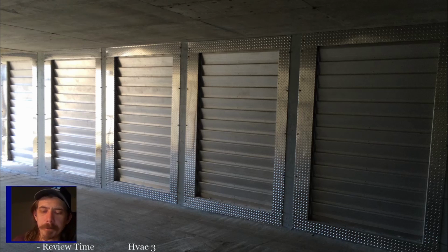So you're going to be troubleshooting them more and more if you do any type of service work. You're going to be installing them more and more if you do any type of installation. Even in commercial, on your smaller units, you're typically going to start seeing ECMs on your condenser fans and your smaller blowers. I wouldn't be surprised if they start making more headway in exhaust fans, because I'm starting to see exhaust fans with variable speed ECMs in them instead of trying to control the output with a belt. So instead of belt drive, you're starting to see ECMs with variable speed controllers for exhaust situations. So it's here to stay, and you have to learn everything you need to do to install them and troubleshoot them.